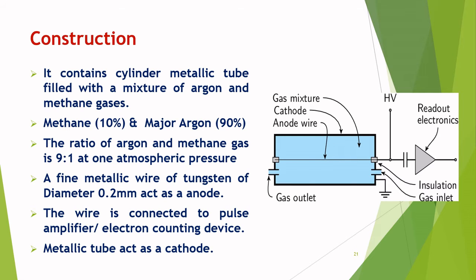Construction. Proportional counters consist of a cylindrical metallic tube filled with a mixture of argon and methane gases. Methane gas is 10%, whereas argon gas is present at 90%. The ratio of argon and methane gas is 9:1, and it is present at 1 atmospheric pressure. A fine metallic wire of tungsten of diameter 0.2 mm is acting as an anode. The wire is connected to the pulse amplifier or electron counting device, whereas the metallic tube is acting as a cathode.